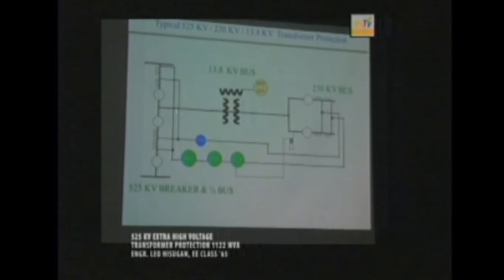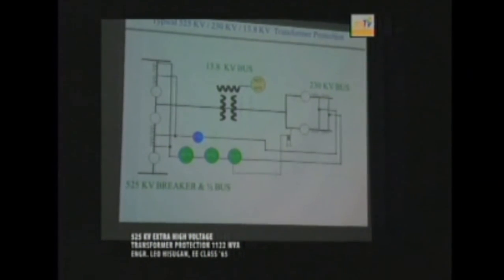And also on this high side of the transformer, you will have a high side overcurrent protection, your 51 device and 50 device. Your 50 device is your instantaneous overcurrent protection, and the 51 device is your time overcurrent protection. The instantaneous overcurrent protection you set at 800% of your full load current for this bank. Your time overcurrent protection is set at around 180 to 210% of your transformer full load current.